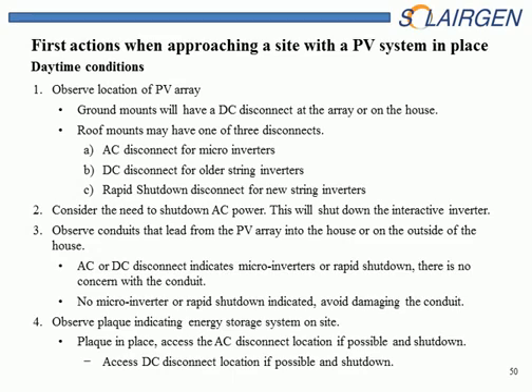Observe the conduits that lead from the PV array to the house and outside the house. If the conduits are running outside, it's very easy to observe. If they're running inside the house, it's a little more difficult to observe unless you know where they're going. And if you don't know where the inverter is located, then that's a bit of a mystery. So an AC or DC disconnect indicates microinverters or a rapid shutdown system, and so there's really no more concern for the conduit. If there's no microinverter or rapid shutdown indicated, avoid damaging the conduit. Try to stay away from it if you can identify its route.